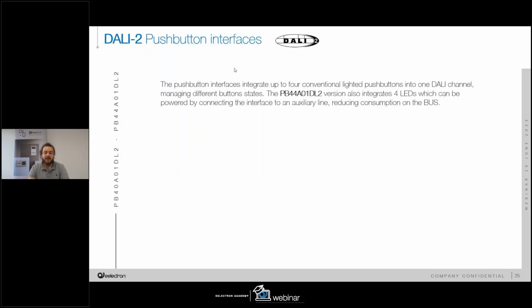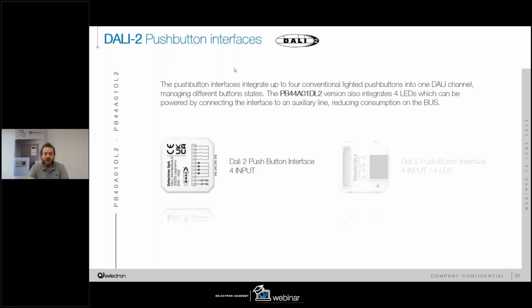Going ahead, we also have the push button for DALI. And here in our catalog, we can see that we have 2 different versions of push button interfaces. The first one is a DALI2 push button with 4 digital inputs. And the second one is again a DALI2 push button interface with 4 digital inputs, but also with the opportunity to have up to 4 outputs for small LEDs. These small LEDs can be powered directly from the device itself. This means that the device will consume a little bit more from the DALI bus, but we also have the opportunity to wire an external power supply to the LEDs.